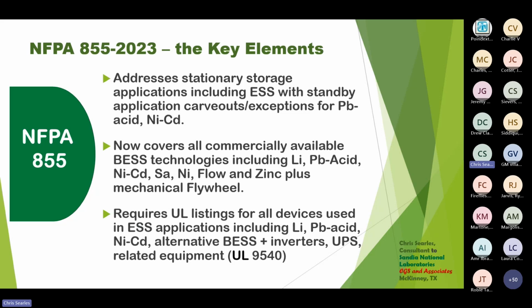It requires UL listings for all devices used in these applications. That includes standby and the new ESS. And it does involve anything that goes into that system, not only the battery, but inverters and UPS devices and controllers and any of the power control equipment, disconnects, all of these. And this is not necessarily introducing stuff that hasn't already been a part of the National Electrical Code. But the bottom line now, it is a part of UL 9540, and it is a requirement in order to pass the testing to get the UL 9540 listing.